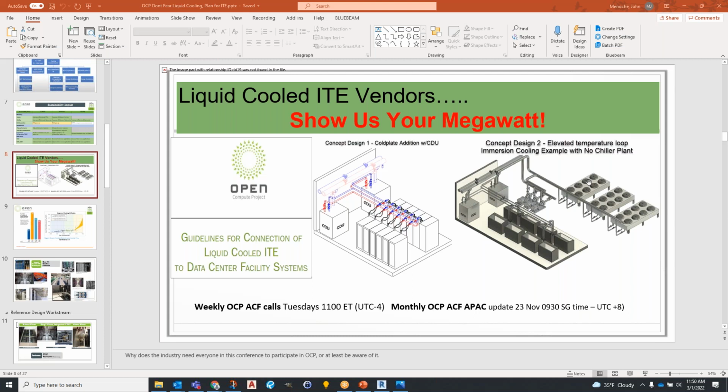I don't know how much impact that information is going to have, as opposed to say a rear door versus a cold plate. And one thing that we need to include in this conversation, John, is going to be the hybrid solutions, right? Because there's a number of solutions out there that are a combination of cold plate and rear door, specifically to address what Otto mentions in here, which is the typical percent capture to liquid.